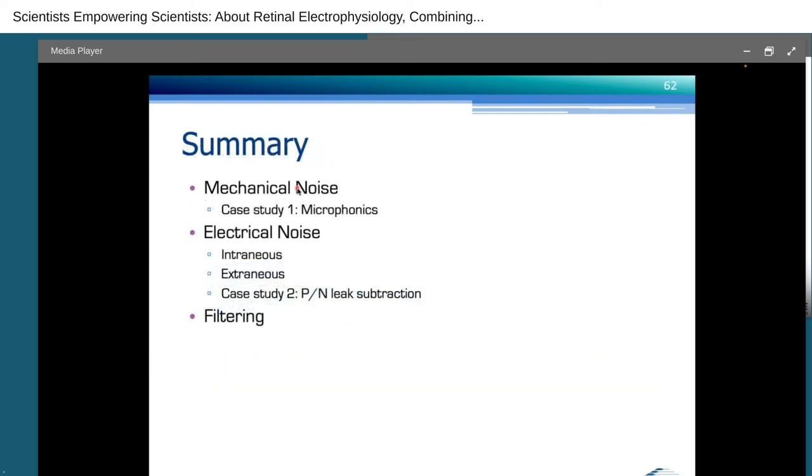If you have to use what's called a hum filter, then you want to use a method that creates a template and subtracts it. That is implemented in the Molecular Devices Digidata 1550, in the Humbug from Quest Scientific that's been around for like ever, and also in software at no additional cost in Sutterpatch software. But my recommendation is don't use it. Notch filters are ineffective and prone to introducing artifacts. So those you definitely don't want to use. You always want to retain the unfiltered signal too. So if you use a hardware item, then record the original signal in addition to the filtered signal. You still want to minimize the noise in your rig first and not rely on the filter alone. The smaller the line frequency hum is that goes into one of these methods, the better the result. And I can only say it again, try to do without. In summary, I talked about mechanical noise, electrical noise and filtering. And now we're going to switch to the question and answer session and the discussion. And I hope there's going to be a lot of interesting questions here. Thank you very much for your attention.